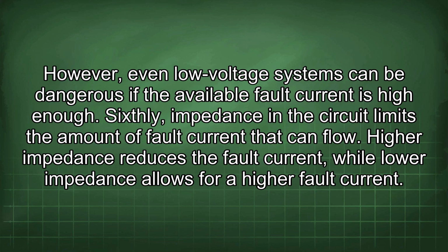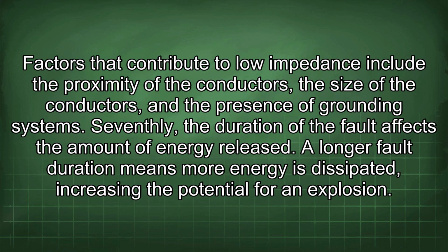Sixthly, impedance in the circuit limits the amount of fault current that can flow. Higher impedance reduces the fault current, while lower impedance allows for a high fault current. Factors that contribute to low impedance include the proximity of the conductors, the size of the conductors, and the presence of grounding systems. Seventhly, the duration of the fault affects the amount of energy released.